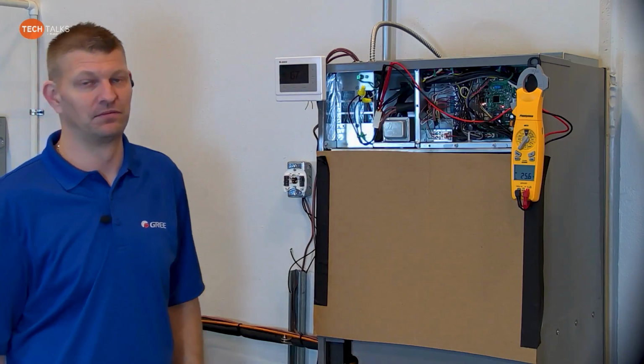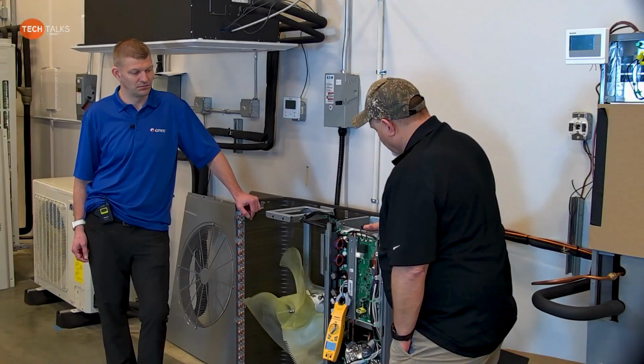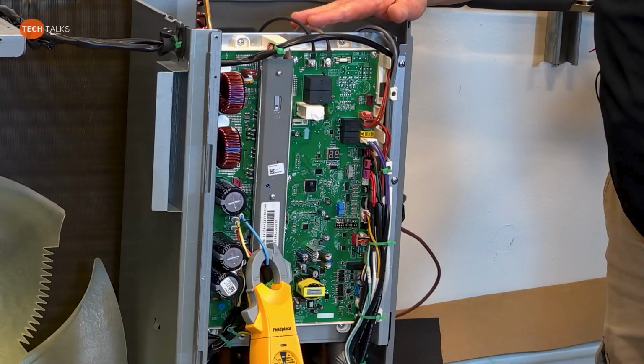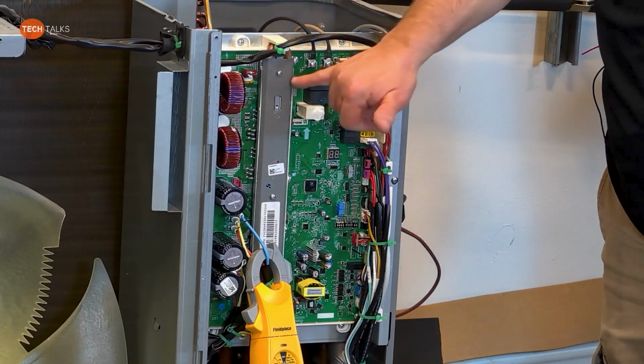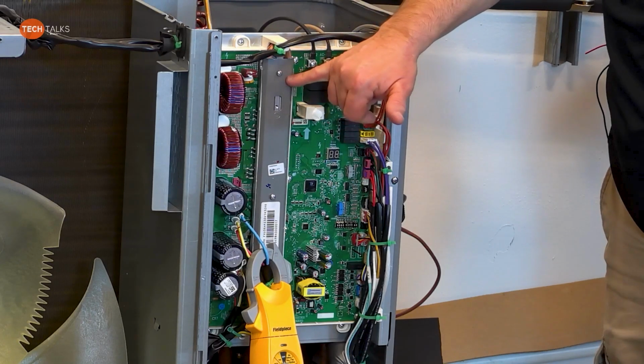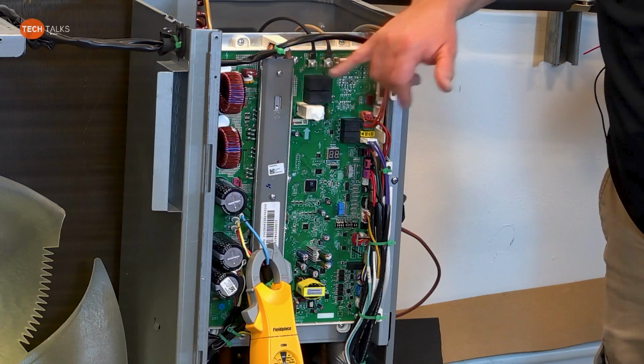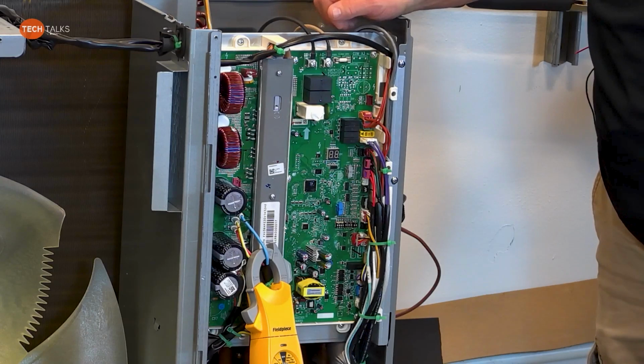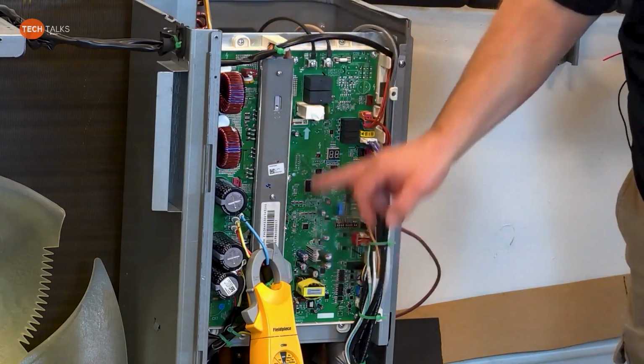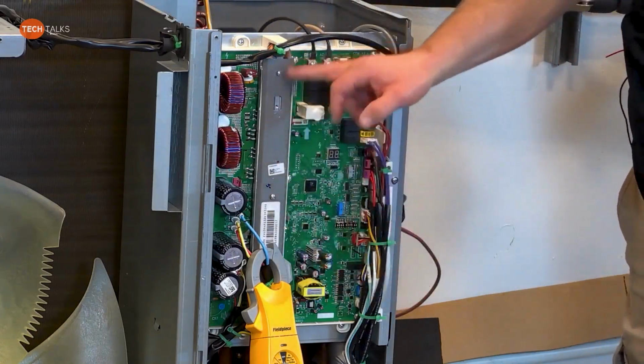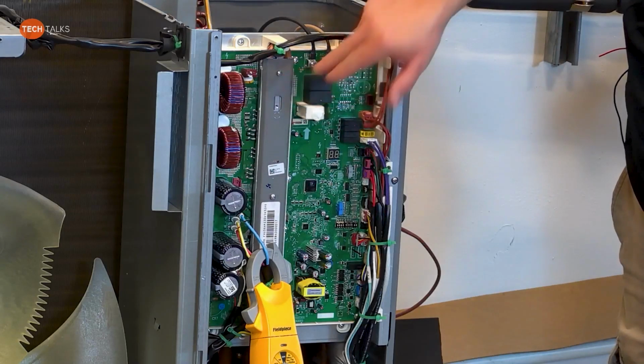Just hit a button, that took away the code, and now we can see our set point. One thing I wanted to point out here on the outdoor unit, I talked about this before, was in that piping diagram that I showed you, where it showed the indoor board module cooling circuit or whatever. That's that liquid loop. In the piping diagram, that's what they're talking about, because this is what's cooling the inverter.